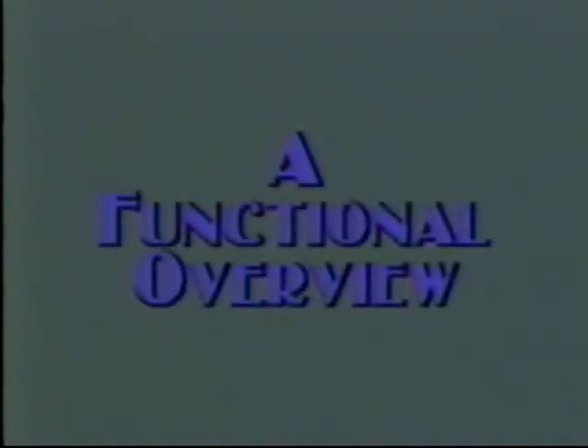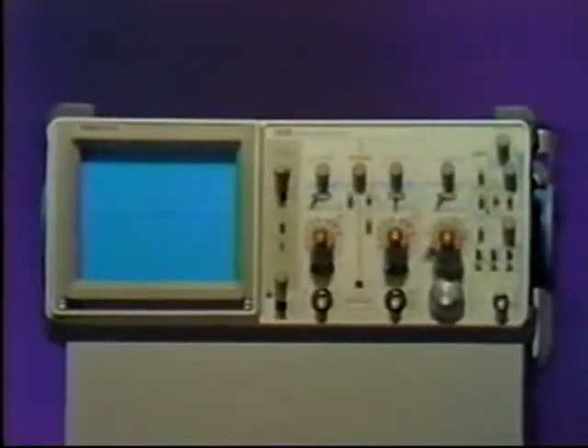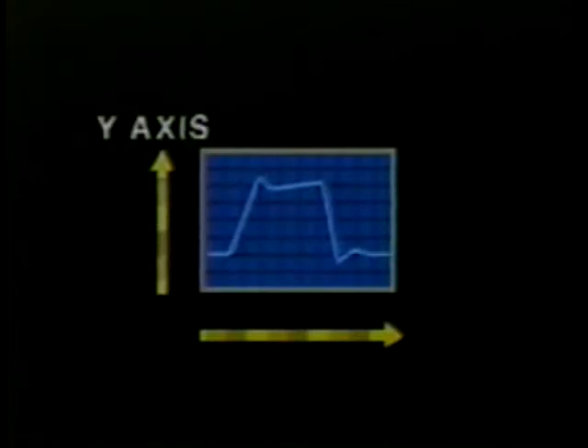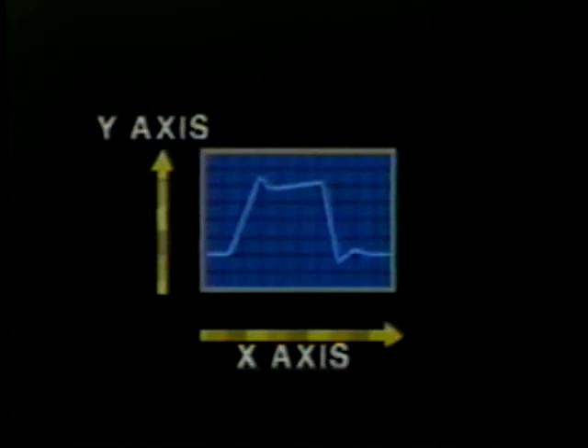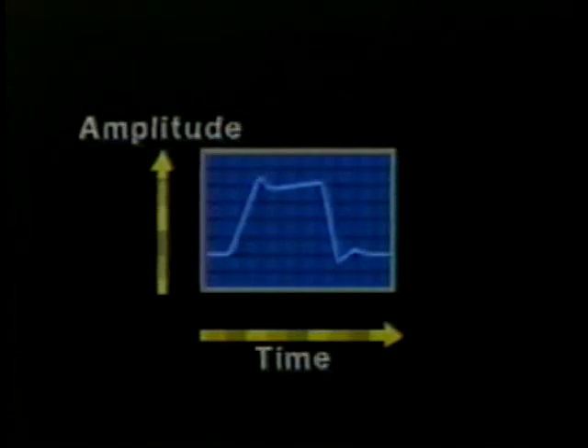With today's diverse technology, the need for viewing electrical phenomena is greater than ever. The device most commonly used to view electrical events is the oscilloscope. Oscilloscopes display electrical events by drawing a graph that shows amplitude on the vertical or y-axis and time on the horizontal or x-axis, so the scope lets us see the amplitude of an electrical event over a calibrated period of time.